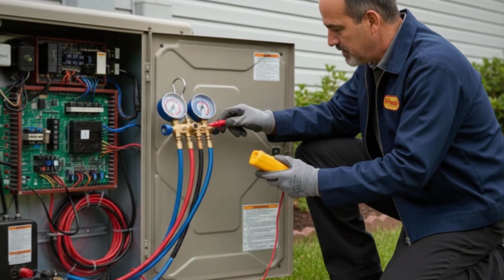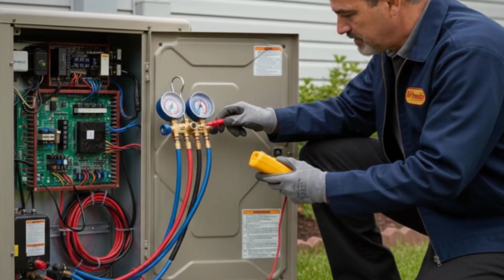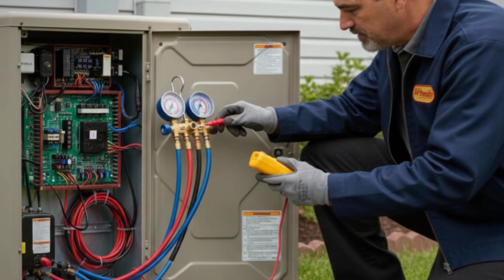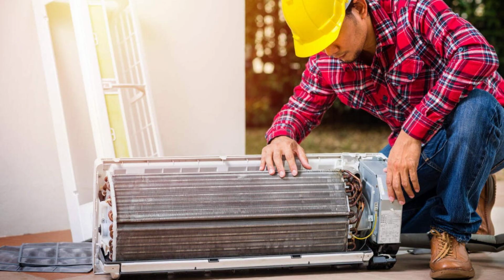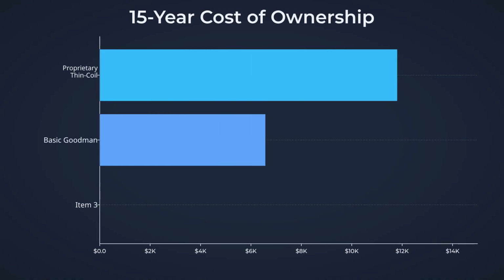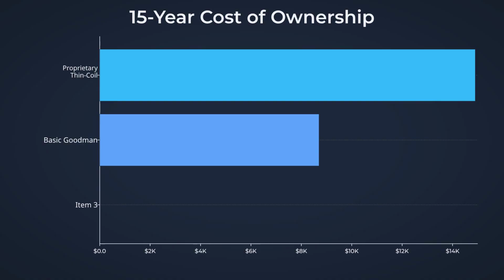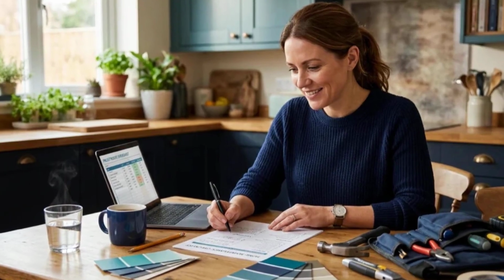You are buying a common architecture with a common repair pathway, serviced by common technicians. If you avoid one proprietary coil nightmare over 15 years, the basic machine wins the lifetime cost math decisively. Expect to pay less upfront and spend dramatically less on the service call that does not turn into a forced replacement.